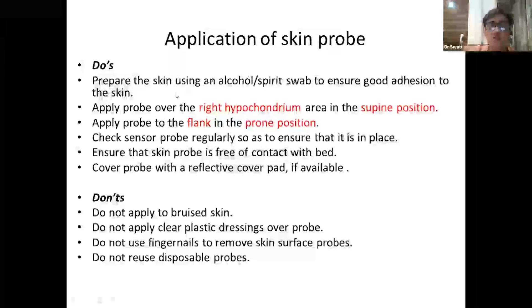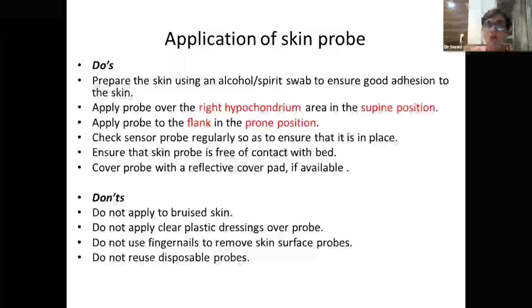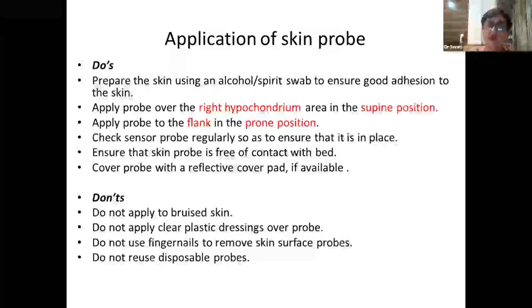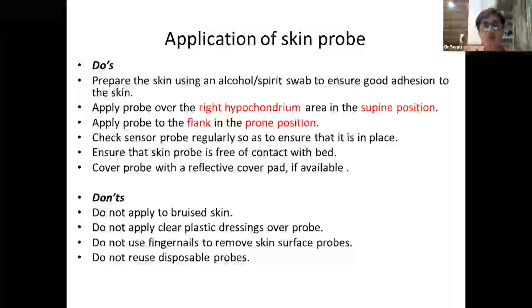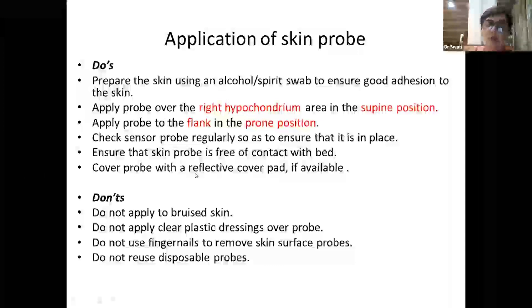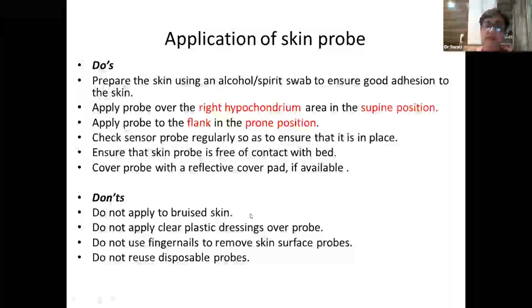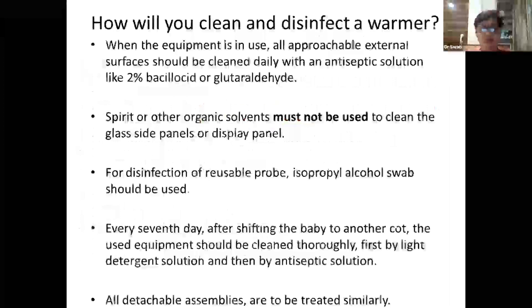For skin probe application: prepare the skin using an alcohol or spirit swab if there is vernix or the area is unclean. Apply the probe to the right hypochondrium in supine position and to the flank in prone position. Check the sensor regularly to ensure the metal surface is flat and in contact with skin. The probe must not contact the bed, and a reflective cover pad may be used. Do not apply to bruised skin or over clear plastic dressings, do not use fingernails to remove the probe, and do not reuse disposable probes.